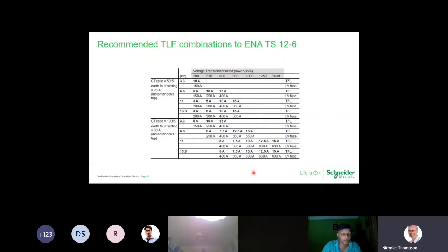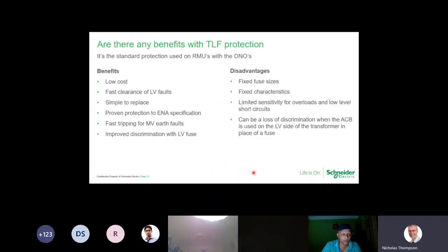It's also very good for coordination on the LV side of the transformer when you've got fuses as the first form of protection on the LV distribution. It becomes more problematic when you've got an ACB. You tend to find problems with coordination with an ACB and time limit fuse. So under those kind of scenarios, the best path would be to move to a self-powered relay like VIP or MiCOM. But then there becomes the aspect of, have you got enough primary current flowing through the ring main unit to power the VIP relay? And that's another subject entirely.